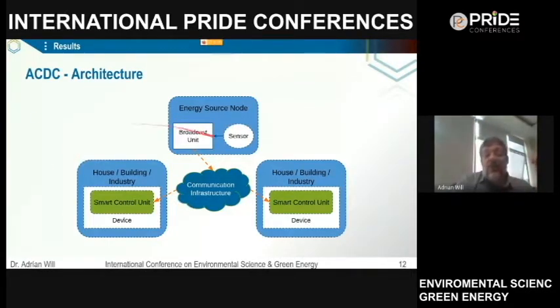So you install a sensor in your transformer, your building entrance line, or your energy source node, your energy supply node, where you get your energy and want to respect your maximum consumption. And you make a broadcast unit that broadcasts your information about consumption every second, every 5 seconds, every 200 milliseconds if you're lucky. Use a communication infrastructure strictly top-down. That means from the source node down to the devices. And every device must have its control unit, gets that information, and makes its decision.